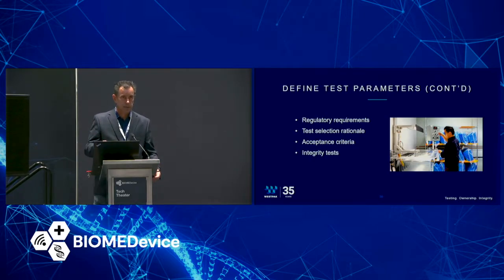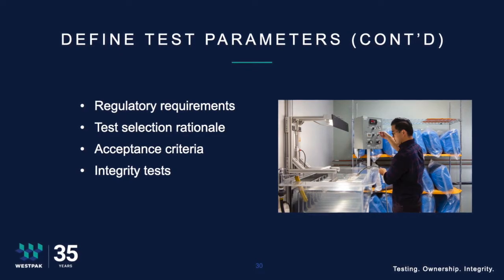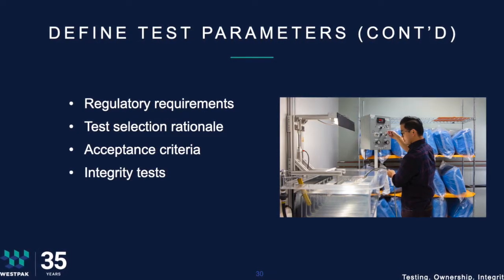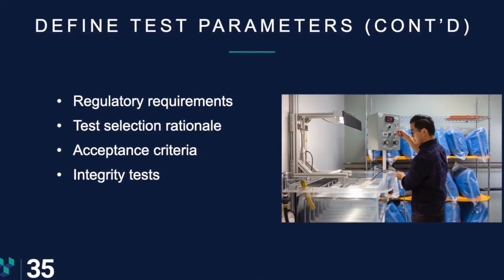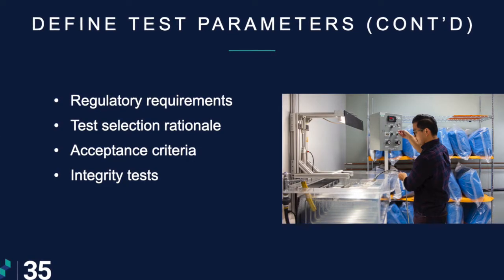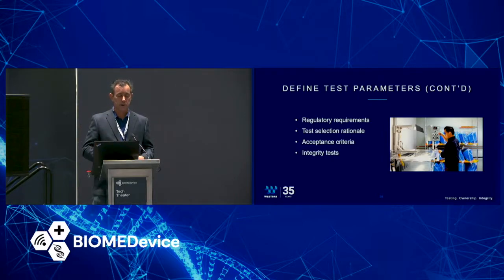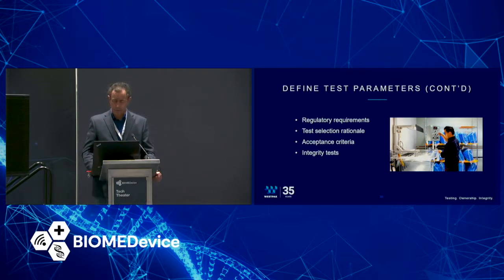For selection of test rationale, you need to create justifications for why you're using a particular temperature range and what your storage condition is. Acceptance criteria is something we're always asked about, and we help our clients determine it — but ultimately that is up to you. Then there are integrity tests: did the aging have an adverse effect on the package or the product? Our main concern is usually the packaging, because we do the bubble leak test and the peel test. Other tests for the product would be done at the client's site.